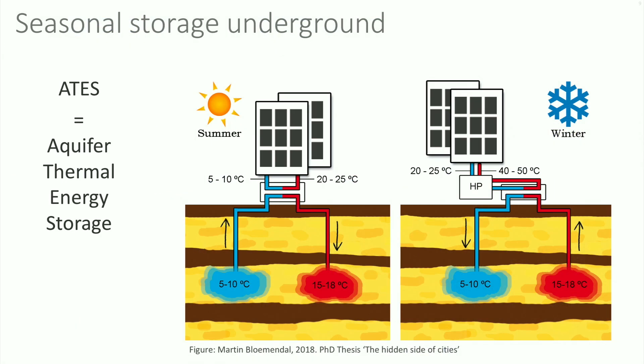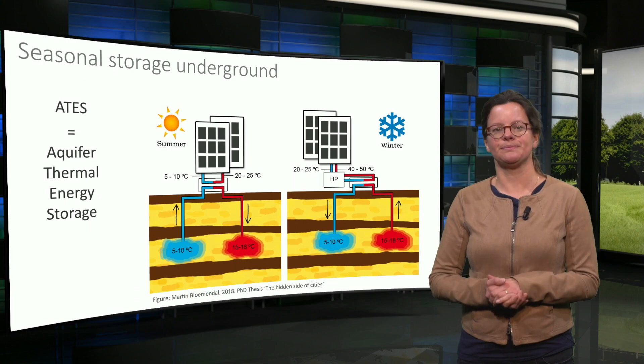In winter the reverse happens. Warm water from the warm well is extracted to be used for heating the building. Since the water stored usually has a maximum temperature of 25 degrees, a heat pump is used to further upgrade the temperature. The cooled groundwater is injected in the cold well again. On an annual basis, the heat and cold extracted must be in balance.